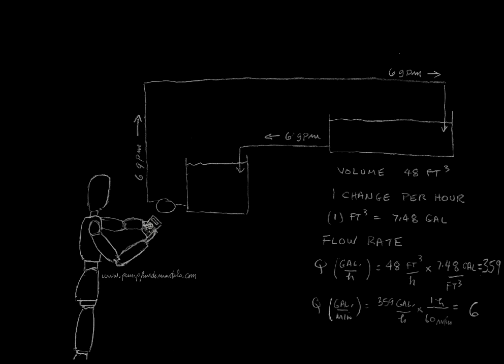The flow rate that will correspond to one change per hour will be 48 cubic feet per hour. I will use gallons instead of cubic feet and there are 7.48 gallons in a cubic foot. Therefore, the flow rate is 48 times 7.48, which is 359 gallons per hour. Let's change this to gallons per minute, which is a very typical unit, although gallons per hour is also used for small pumps. Which means I divide 359 by 60, since there are 60 minutes in an hour, and I get 6 gallons per minute.